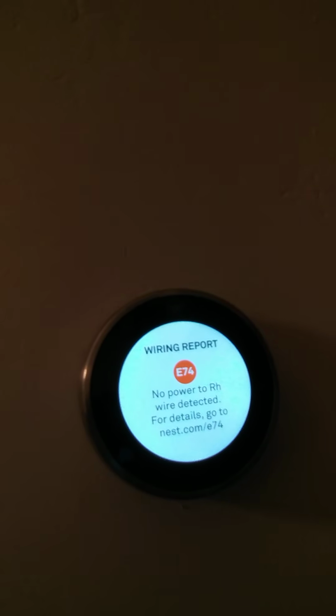You can see that E74 error code. Basically what it's saying is there's no power being supplied to the actual thermostat. So naturally you might think, okay, maybe the power wire that runs from the furnace itself up to the thermostat has lost connection somehow, or it's bad wiring, and you might need to run a new wire. It's possible, but that would be very rare for a situation like that to occur. That was not the issue with my system, but in essence what it's saying is that it does not have power being supplied from the heater unit to the thermostat, so there's a breakage somewhere in the wiring.